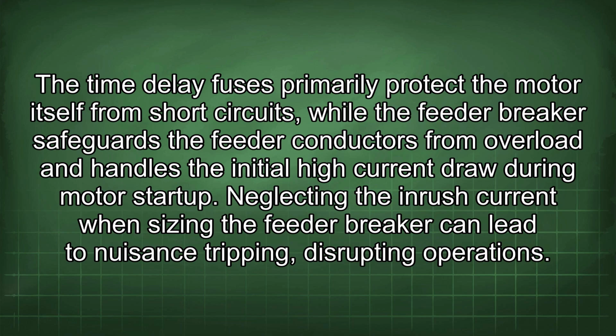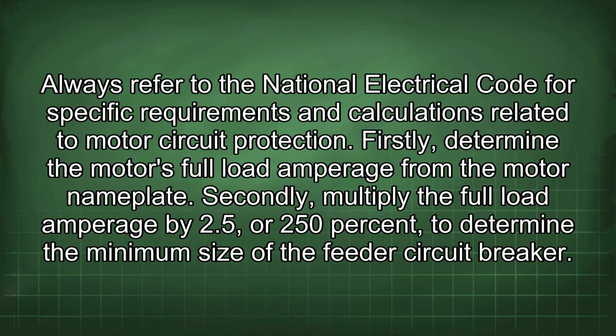The time delay fuses primarily protect the motor itself from short circuits, while the feeder breaker safeguards the feeder conductors from overload and handles the initial high current draw during motor startup. Neglecting the inrush current when sizing the feeder breaker can lead to nuisance tripping, disrupting operations. Always refer to the National Electrical Code for specific requirements and calculations related to motor circuit protection.